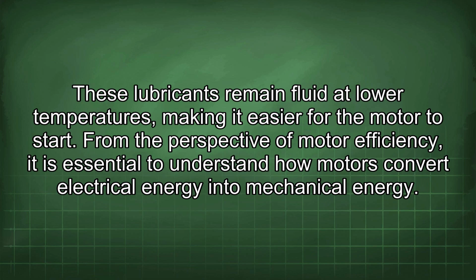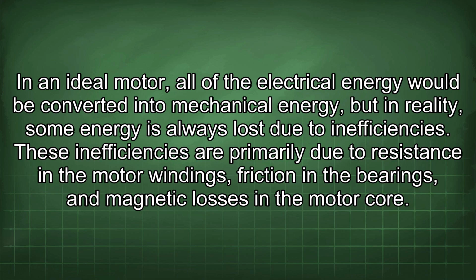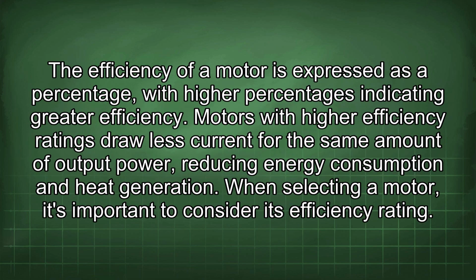From the perspective of motor efficiency, it is essential to understand how motors convert electrical energy into mechanical energy. In an ideal motor, all of the electrical energy would be converted into mechanical energy, but in reality, some energy is always lost due to inefficiencies. These inefficiencies are primarily due to resistance in the motor windings, friction in the bearings, and magnetic losses in the motor core. The efficiency of a motor is expressed as a percentage, with higher percentages indicating greater efficiency. Motors with higher efficiency ratings draw less current for the same amount of output power, reducing energy consumption and heat generation. When selecting a motor, it's important to consider its efficiency rating.